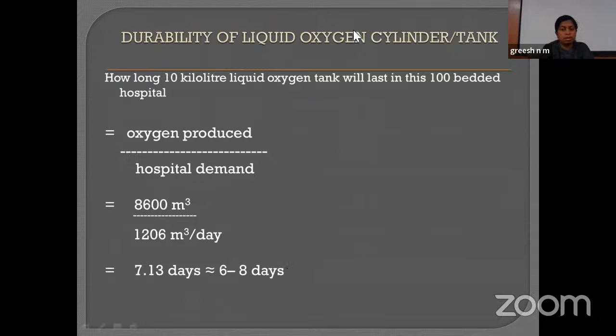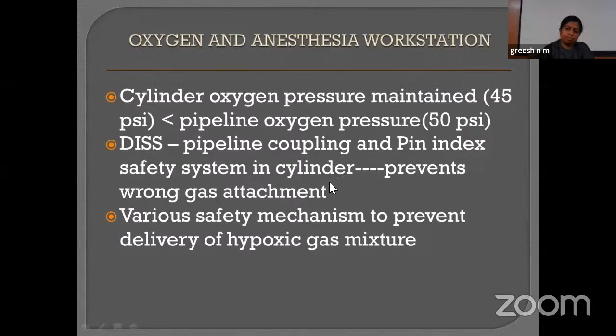So far we have discussed oxygen with cylinders and the liquid oxygen tank. Now something regarding oxygen and the anesthesia workstation. In the anesthesia workstation, there is a provision such that the cylinder oxygen pressure is always maintained lesser than the pipeline oxygen pressure. This is for preferential use of pipeline oxygen rather than cylinder oxygen by the workstation. There is a diameter index safety system for the pipeline coupling and a pin index safety system for the cylinders. All this prevents the attachment of the wrong gas. And there are various safety mechanisms in the workstation to prevent delivery of a hypoxic gas mixture to the patients.